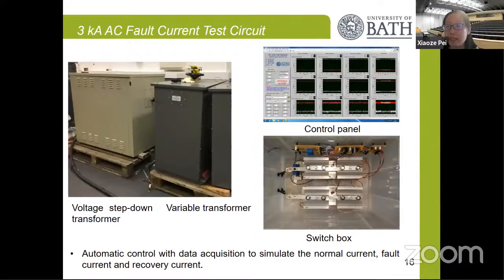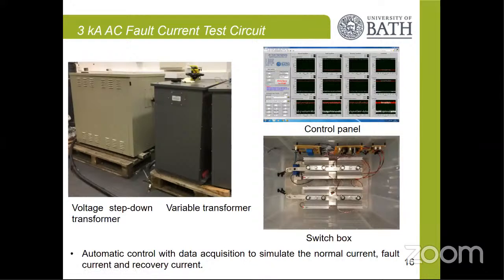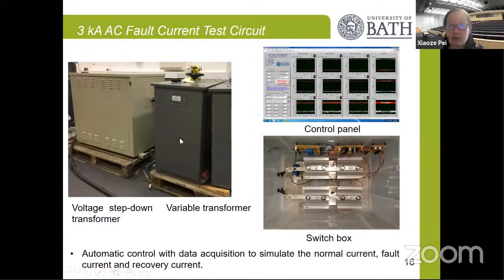And then a second important area would be, how does it respond to a fault current? What is the response time, and how long does it take when the fault is cleared in the system? So in the lab, we developed a 3 kiloamp AC fault current limiting test circuit. We developed a program that controls some of the switch boxes to simulate the normal operation, then the fault condition, and then the recovery condition. We can set the length of the fault duration as a parameter and observe the recovery as well.